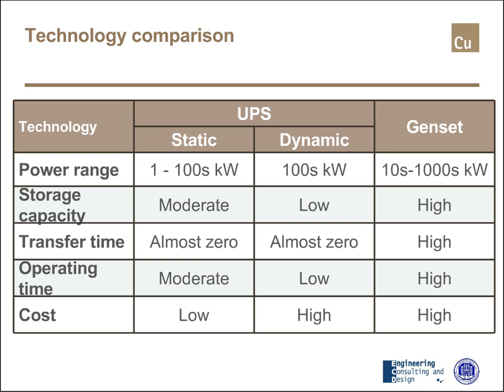These are different technologies with different pros and cons. Static UPS covers a very large power range, from nominally one kilowatt to some hundreds of kilowatts. Dynamic UPS are available from around one hundred kilowatts, or probably two or three hundred. Gensets are available from tens of kilowatts to some megawatts. The storage capacity is high for static UPS, low for dynamic UPS, and theoretically infinite for gensets.